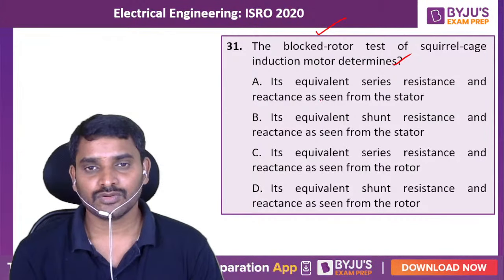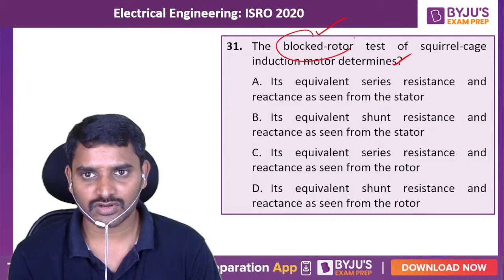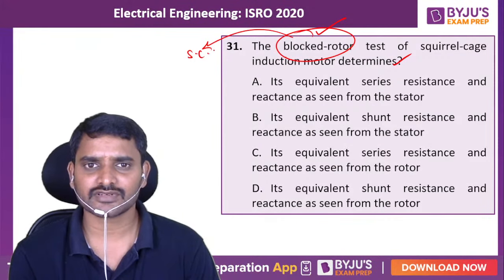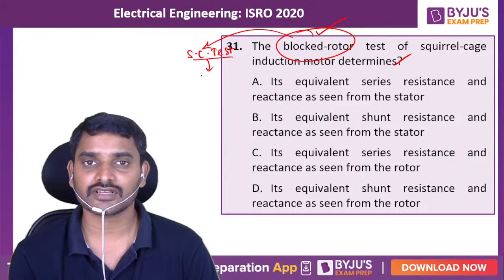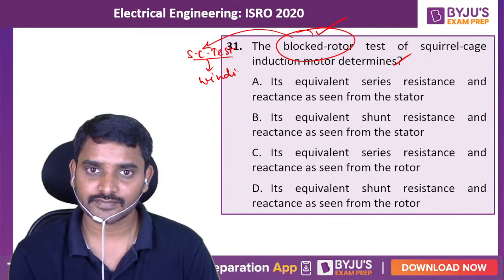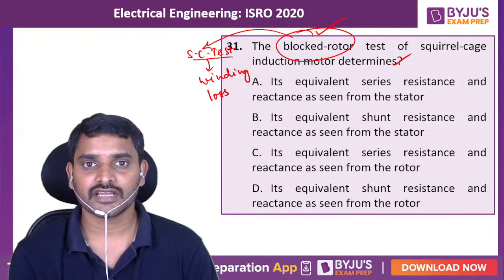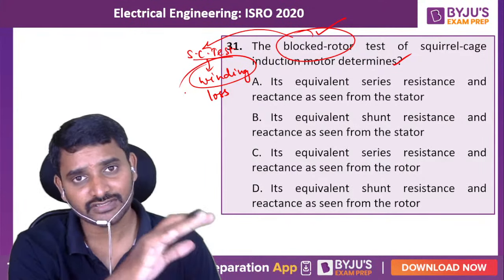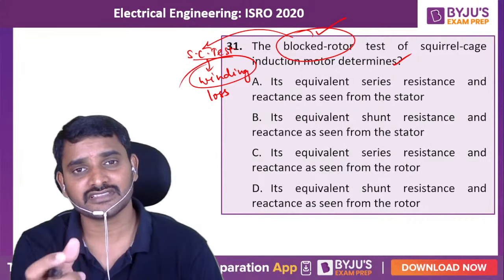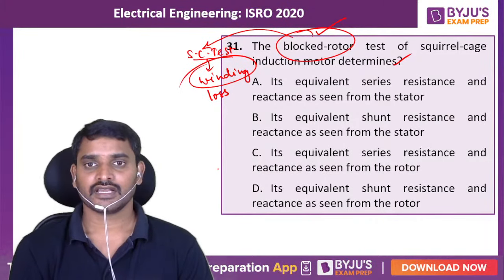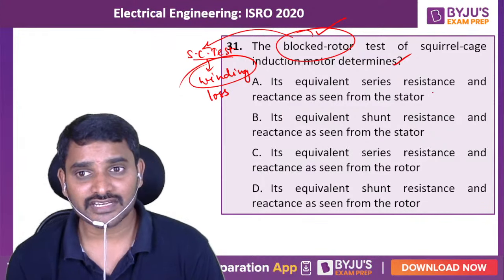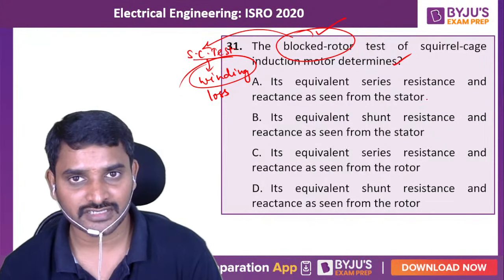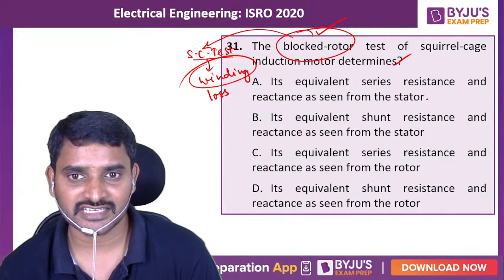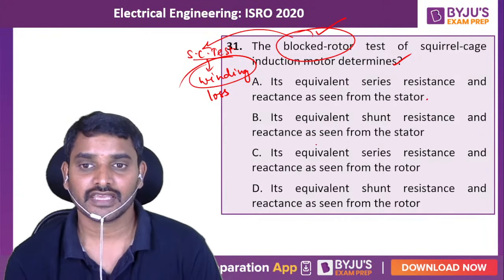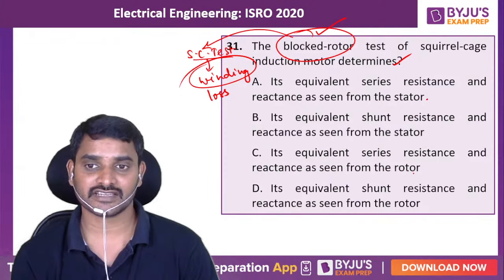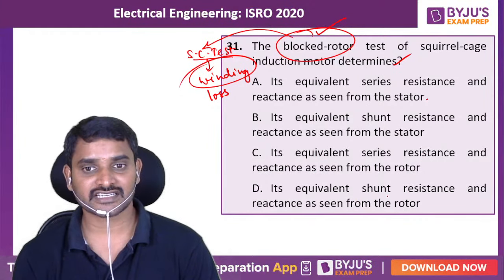Now, I am trying to say that the blocked rotor test is equivalent to the short circuit test of a transformer, and you are going to find out the winding losses simply. Where is the winding? The winding is there on the stator as well as the rotor. So you can see the stator winding parameters and the rotor winding parameters. It is going to determine the equivalent series resistance and reactance as seen from the stator, the equivalent shunt resistance and reactance as seen from the stator, the equivalent series resistance and reactance as seen from the rotor, and the equivalent shunt resistance and reactance seen from the rotor.